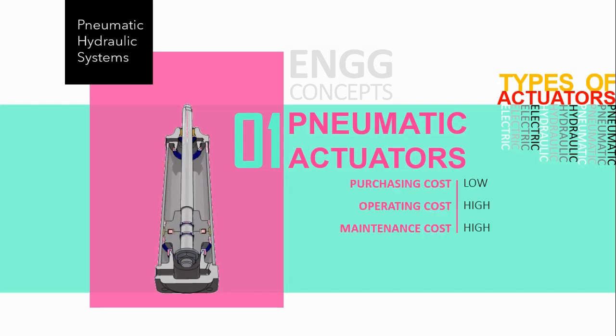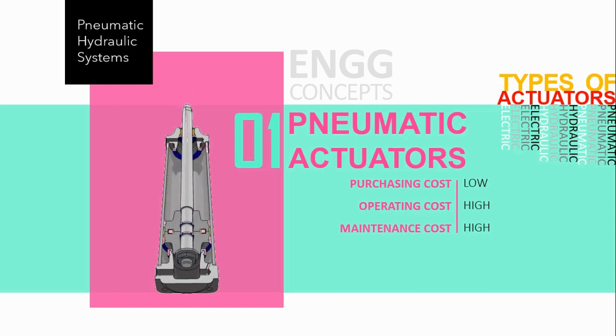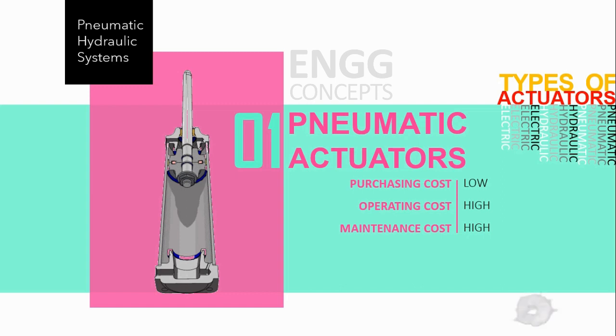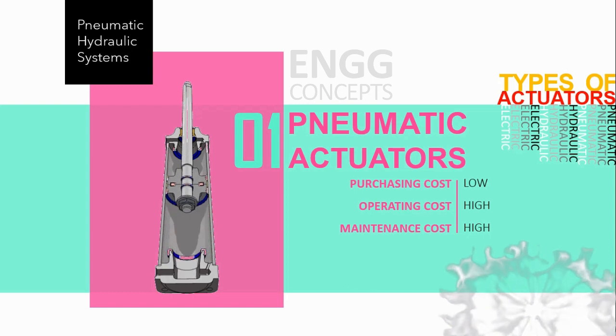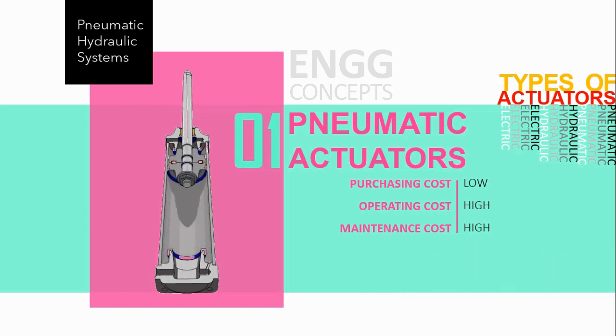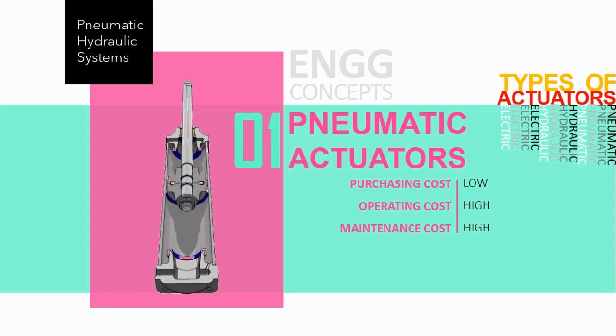Out of all three types of actuators, pneumatic actuators cost less upfront than the other types. However, the operating cost is high because you also need to install an air compressor to generate clean and dry compressed air. When it comes to maintenance requirements, the price is highest of all three actuator types, as we need to install the compressor in a well-ventilated area, most preferably outside, and we need extra piping and so on.